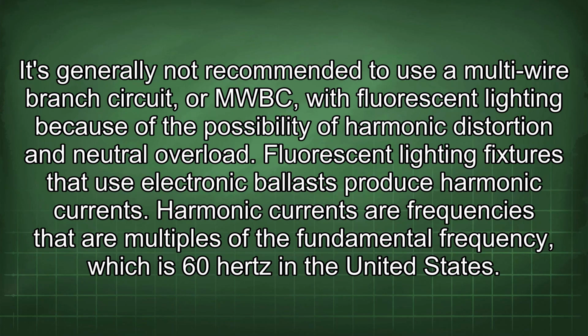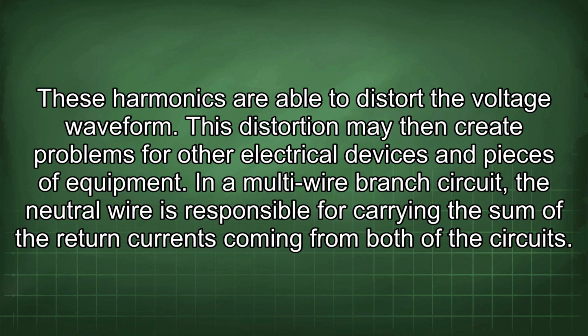It's generally not recommended to use a multi-wire branch circuit, or MWBC, with fluorescent lighting because of the possibility of harmonic distortion and neutral overload. Fluorescent lighting fixtures that use electronic ballast produce harmonic currents. Harmonic currents are frequencies that are multiples of the fundamental frequency, which is 60 Hz in the United States. These harmonics are able to distort the voltage waveform. This distortion may then create problems for other electrical devices and pieces of equipment.